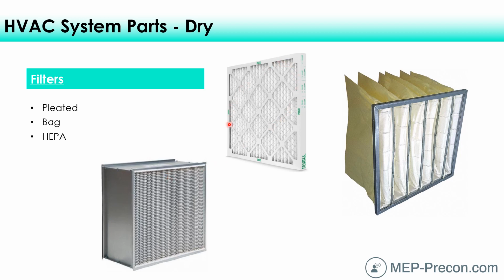These pleated filters are not very efficient, maybe 30% efficient, and these bag filters are somewhere in between, maybe 70 to 80% efficient, something like that.